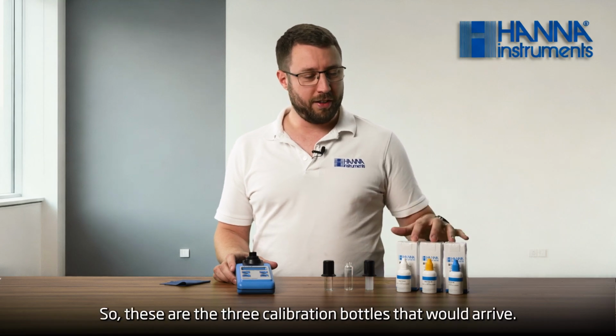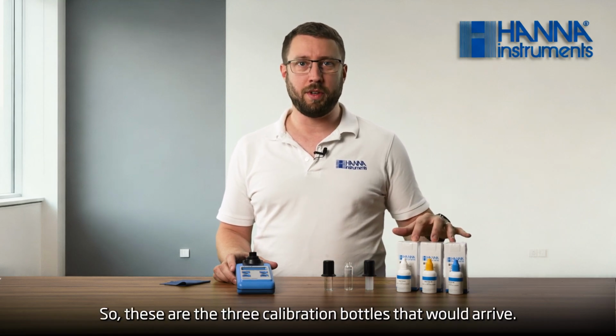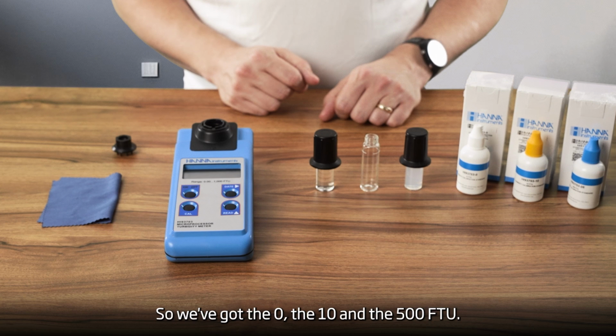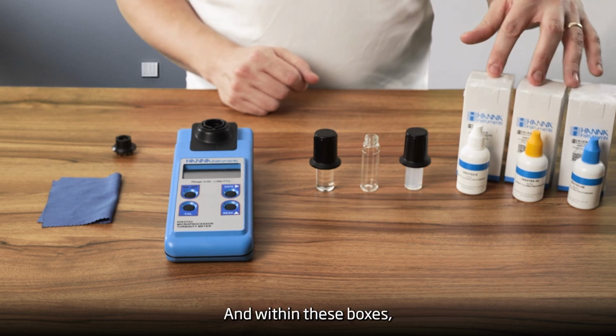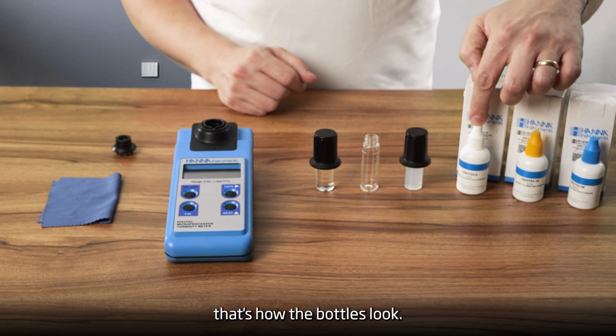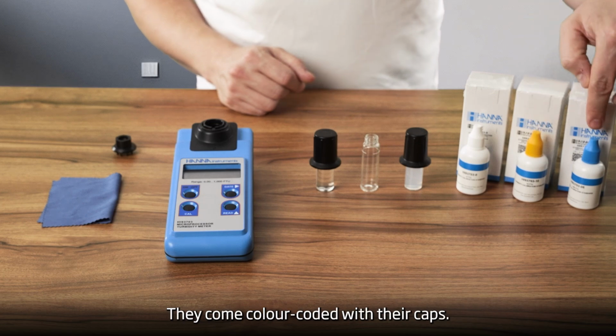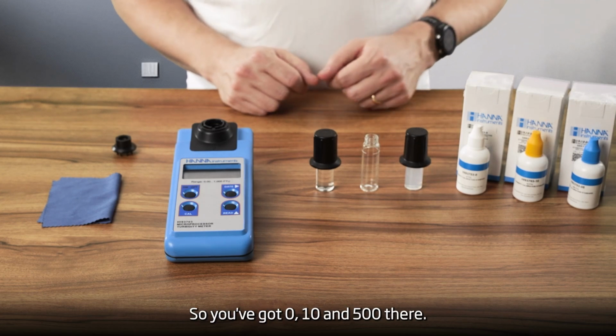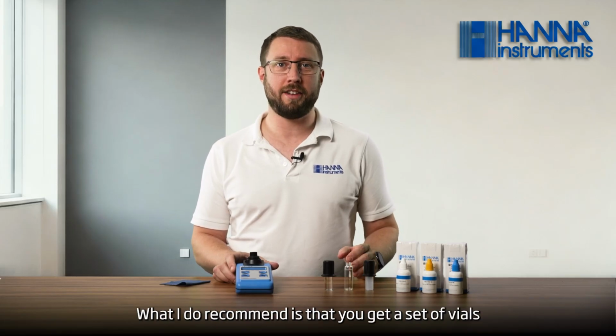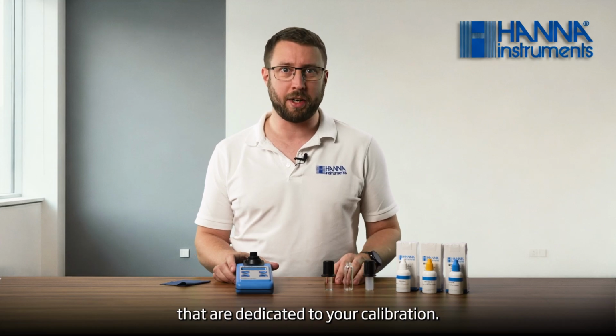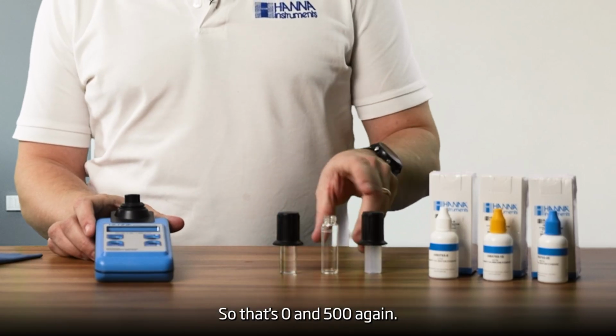So these are the 3 calibration bottles that would arrive. So we've got the 0, the 10 and the 500 FTU, and within these boxes that's how the bottles look. They come colour coded with their caps, so you've got 0, 10 and 500 there. What I do recommend is that you get a set of vials that are dedicated to your calibration. So that's 0 and 500 again.